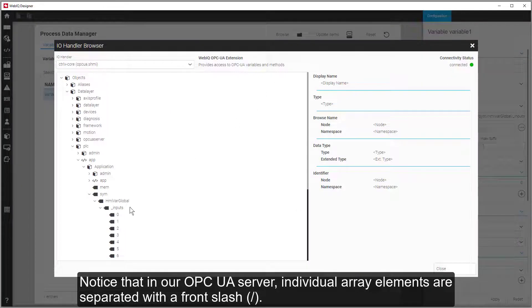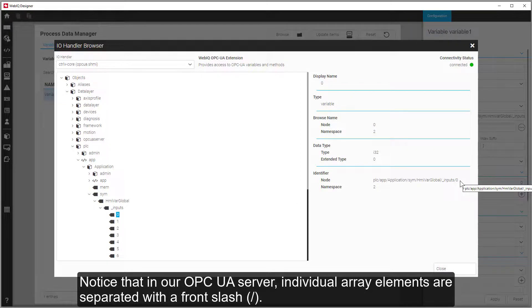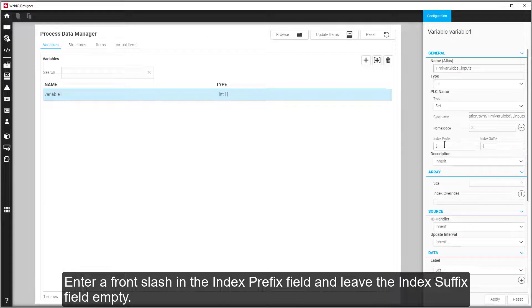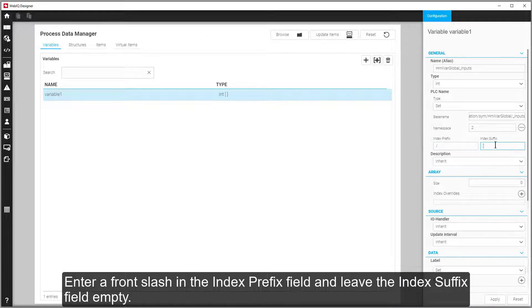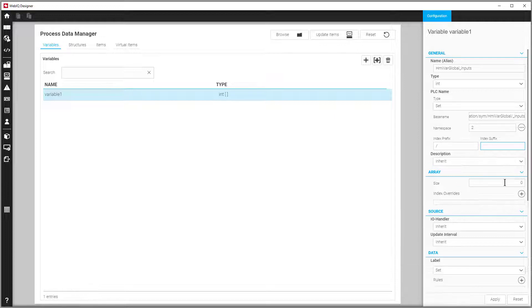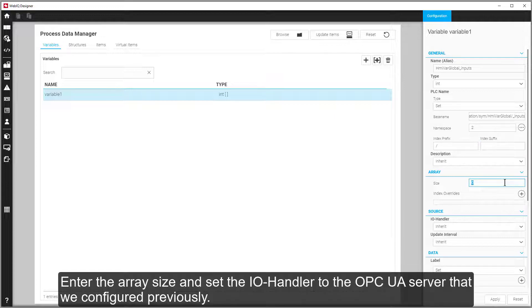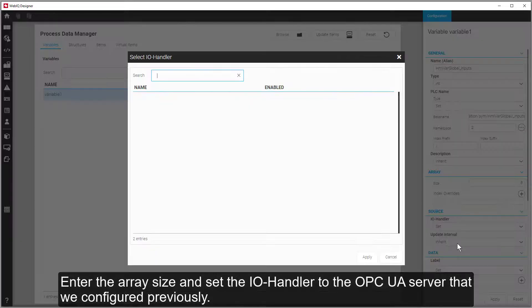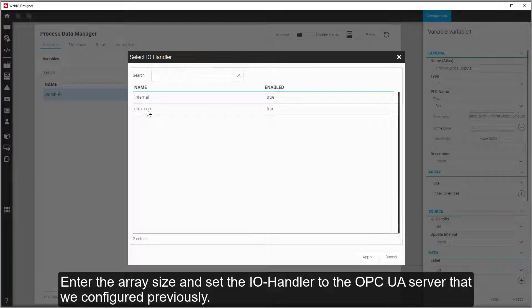Notice that in our OPC UA server, individual array elements are separated with a forward slash. Enter a forward slash in the index prefix field and leave the index suffix field empty. Enter the array size and set the IO handler to the OPC UA server that we configured previously.